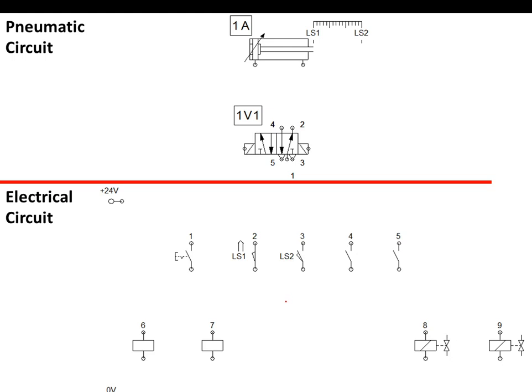We now arrive at the Fluid SIM drawing area where we place our pneumatic and electrical components. We need a double acting cylinder — make sure it is double acting — and a 5/2-way DCV with double solenoids. Make sure each component has its own label: A refers to the actuator, V1 refers to the control element, and label the solenoids Y1 and Y2.